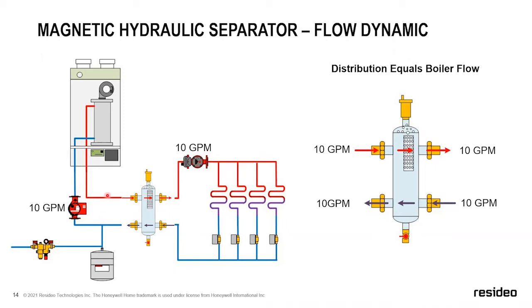And the reason for that is, and I'm going to use this in the next three examples, but when a boiler specifies a pump, sometimes they'll list the flow rate they want to see. More commonly, they just tell you, use this pump on this speed. And the reason, what they're doing there is, with these newer boilers, they need to make sure, and I guess they're not really newer anymore, they've been around for a long time now, but there's not a lot of water volume in here.